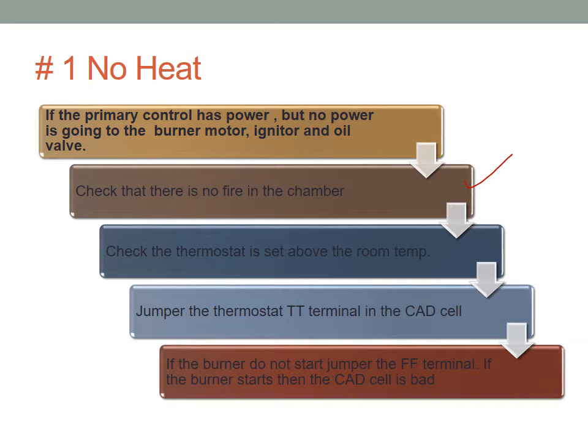Check the thermostat and make sure it's set above the room temperature. If you put it at 70 and the room is already at 70, it's not going to click. So you can turn it up and see, and you can also jumper that to see if it's working or not. Jumper the thermostat terminals and check if they are working or not. So again, that's another way to troubleshoot. We did some troubleshooting while we were in the boards, but it's different in real life, a little bit, not a lot, but it should be similar. So check the thermostat, make sure the thermostat is functioning, and if you jumper the equipment and it comes in, that means something is wrong with the thermostat.